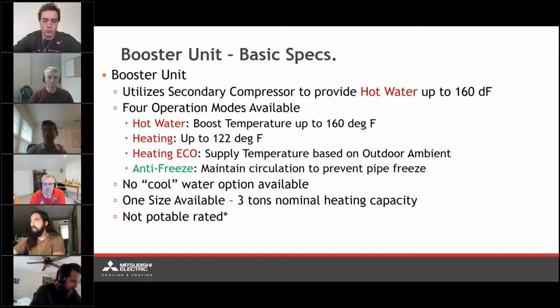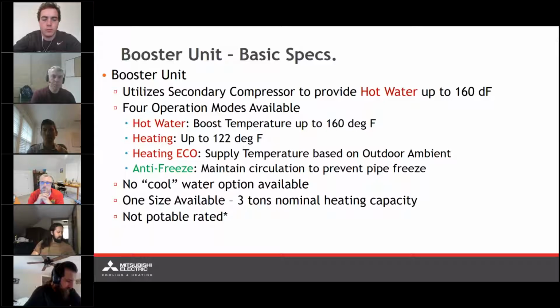Now, the booster unit, unlike the HEX auxiliary unit, cannot provide cooling for the water loop that it's connected to, since the R134A loop within it does not contain a reversing valve. So we don't need to worry about that application with the aux unit. In the booster unit itself, there is no reversing valve to allow for a cooling process. That said, as with the HEX auxiliary unit, this can be connected onto any VRF system or any three-phase City Multi VRF system with other fan coils. The only limiting factor is connection ratios. Ultimately, we're going to work with any customer looking to design this process, working very closely to make sure that everything's designed properly and sized accordingly.